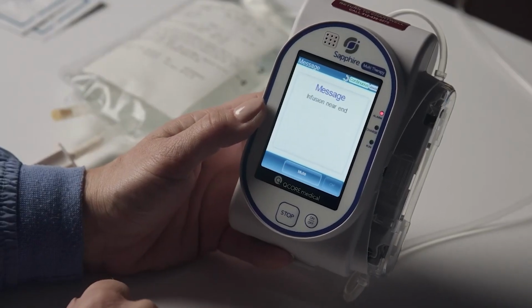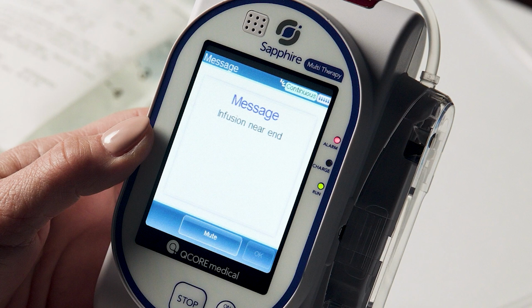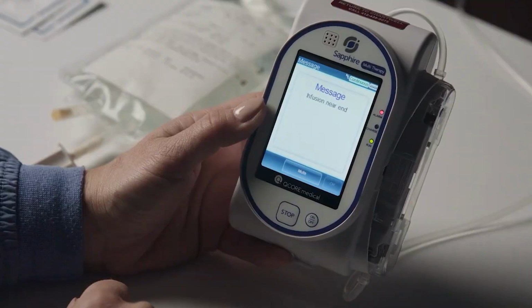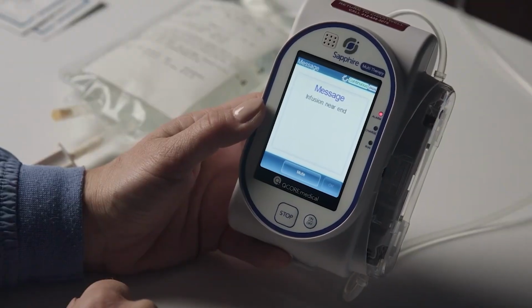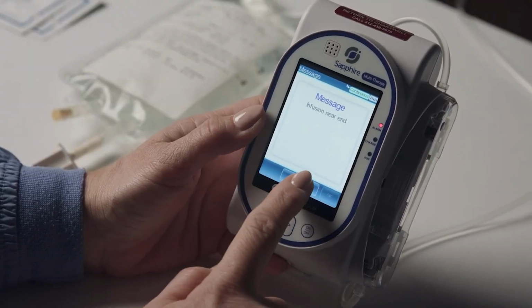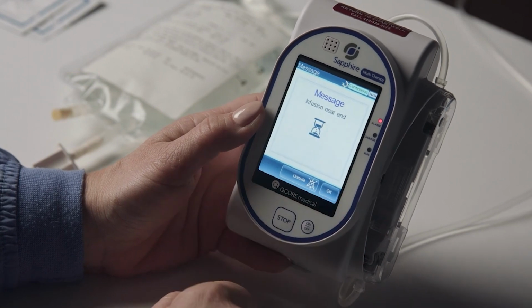When your infusion is nearing completion, an alarm may sound and you will see the message display, "Infusion near end." This is designed to give you a warning 10 minutes prior to infusion completion. To clear this message and the alarm, press Mute and then press OK.